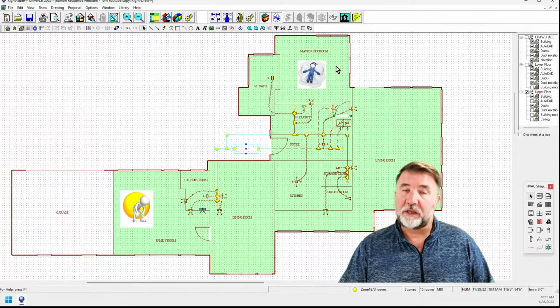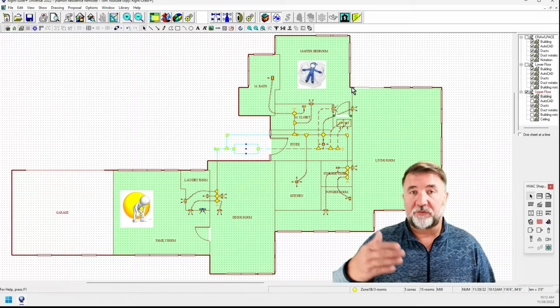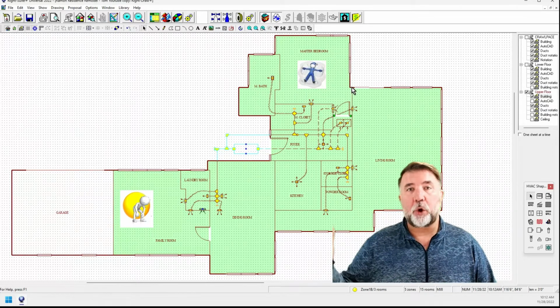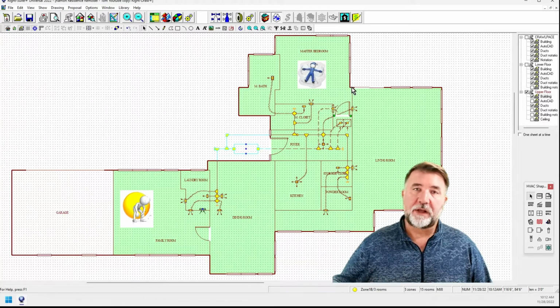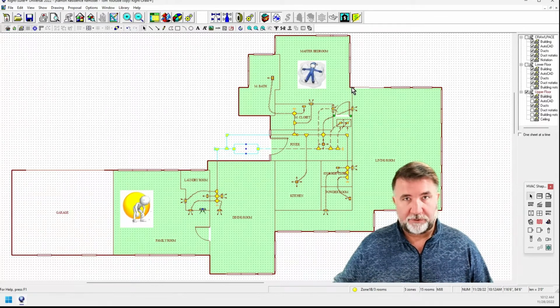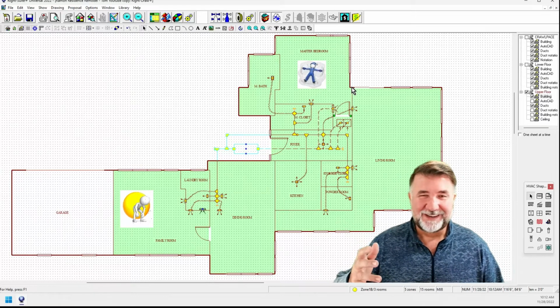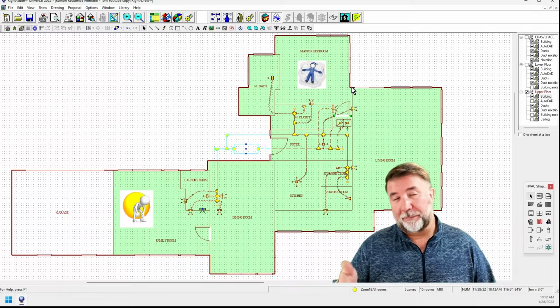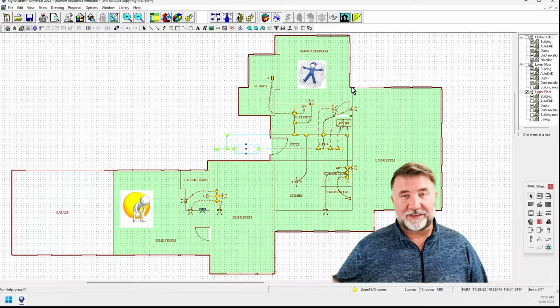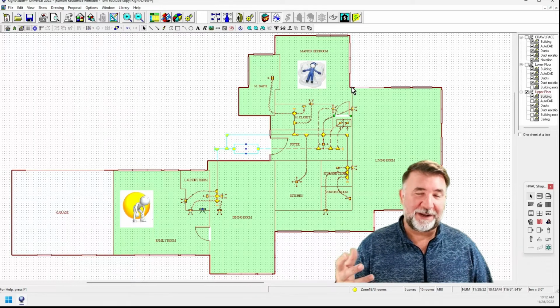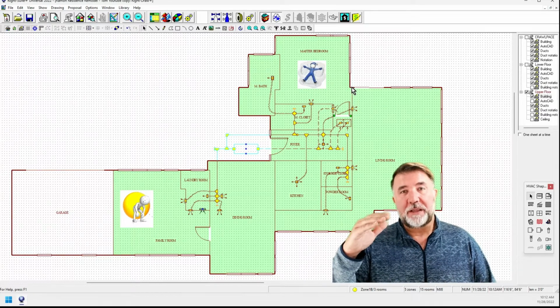If it's designed properly, the humidity throughout your house should be between 45 and 55 percent. If it's over 60, you're going to have mold growth. If it's under 40, you're probably in Arizona. Okay, you don't have to worry about it too much. Or it's wintertime out. But heck, even in Florida when it's winter out, I think it's still above 40% humidity. So you've got to keep it in that range.